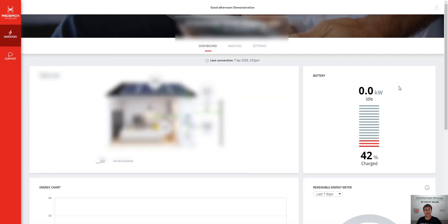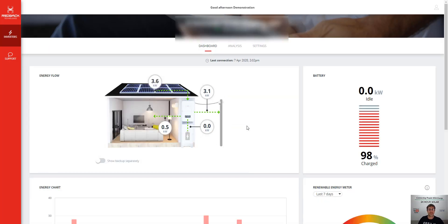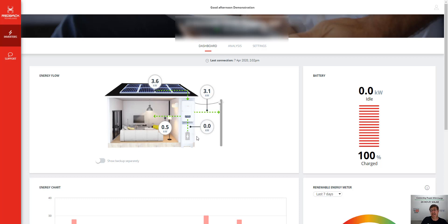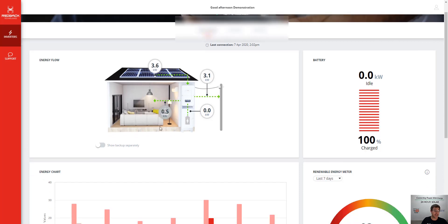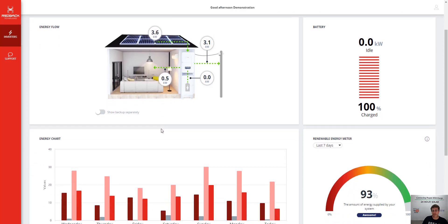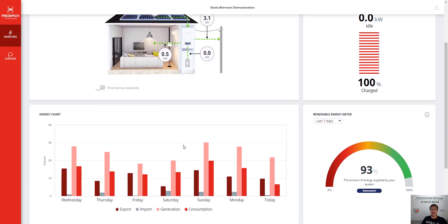So we have a couple of different inverters we can have a look at here. Let's have a look at this one here. Cool. So this one here, 3.6 kilowatts the solar panels are doing, 3.1's going back to the grid. This customer is drawing nothing from batteries, and they're using half a kilowatt in the house here. So it's really great monitoring.